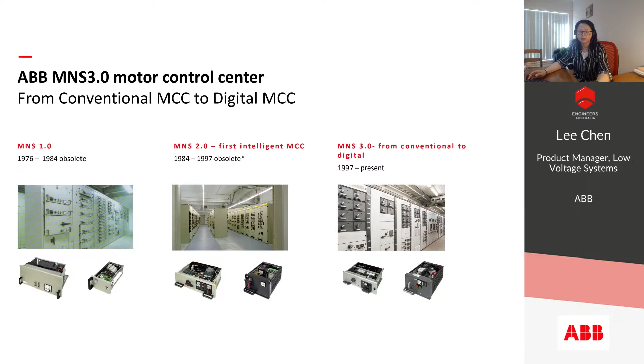The intelligent MCC offered by ABB MNS3 today is a solution built on the ABB Smart Motor Controller device, UMC 100.3 or M10X. The intelligent motor starter, compared with a conventional starter, delivers significantly more value, especially in simplicity, safety, and functionalities. The example here is a quick comparison of the difference. Other than the power switching device, most of the associated control, measuring, signaling, and protective devices are replaced by one single smart controller.